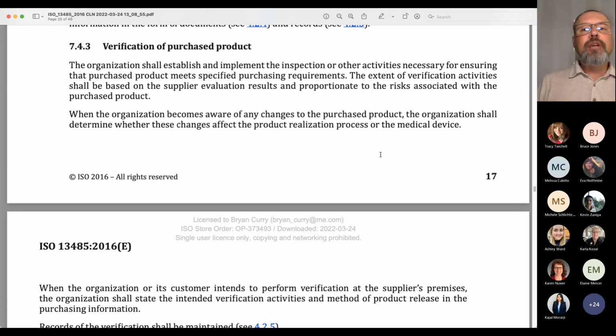If we are using inspection criteria to determine whether or not materials or components meet the acceptance criteria we gave the supplier, the methods that we use to perform that assessment should be validated. That can mean a lot of different things. If you are a part of an incoming quality control group and you are using a set of calipers to do that acceptance activity, well, we might not have a full-blown test method validation for calipers. We probably just have a gauge R&R. But if we're using a smart scope with a programmed routine, or if we're using some kind of functional piece of test equipment that was provided by the supplier, we might have more formal validations for some of those types of receiving inspection activities.